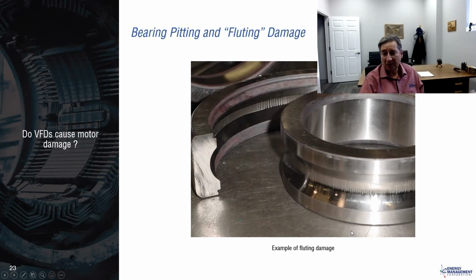Now, of course, if someone lets us go too long, the bearing will fail, the rotor may crash into the winding, and then you have a total catastrophic failure. So probably, I don't remember the percentage, we figure the majority of electrical motor failures are mechanical failures, but many of them cascade into electrical failures.